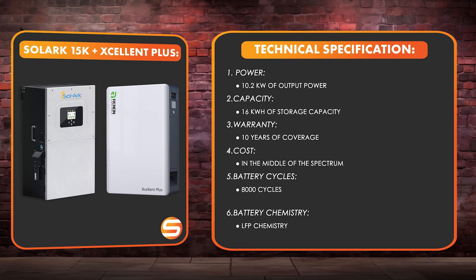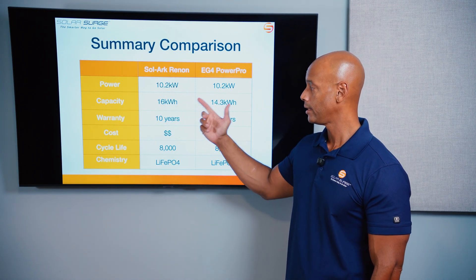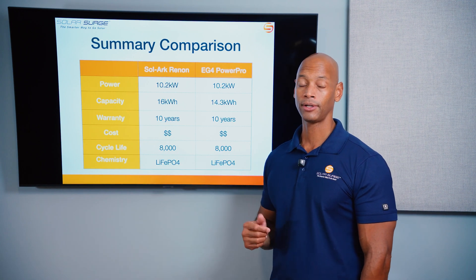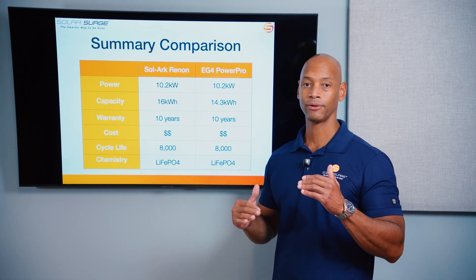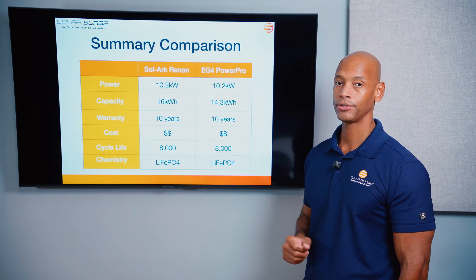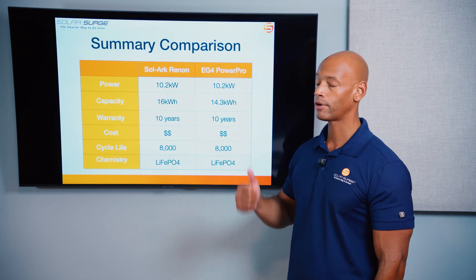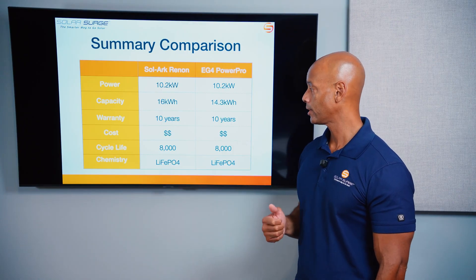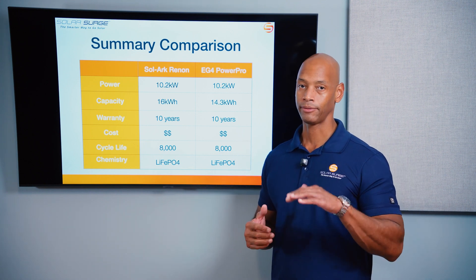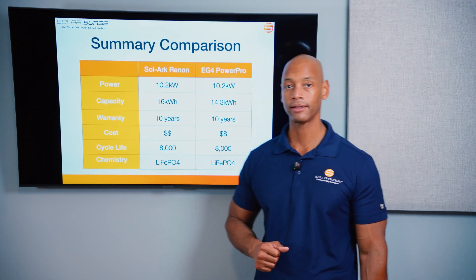To summarize: both systems are very similar. The Sol-Ark Renon combination offers 10.2 kilowatts output power per battery, 16 kilowatt-hours of storage per battery, a 10-year warranty, 8,000 cycles, and lithium iron phosphate chemistry — with slightly higher inverter cost but slightly lower battery cost. The EG4 PowerPro system also delivers 10.2 kilowatts output (200 amps max continuous draw), 14.3 kilowatt-hours of storage per battery, a 10-year warranty, and 8,000 cycles with LFP chemistry — with lower inverter cost but slightly higher cost per kilowatt-hour on the battery.